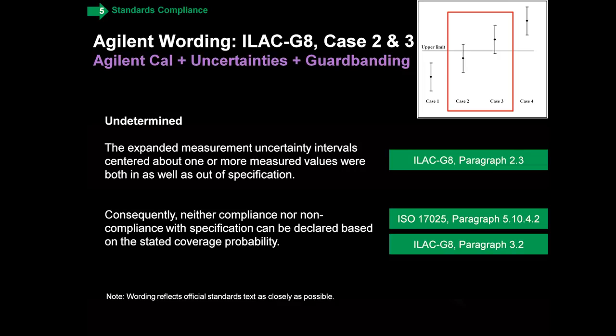There is also a service called 'Agilent Cal Plus Uncertainties Plus Guard Banding,' and this one gives pass or fail — or in the case of either case two or case three, where you measure just inside or just outside but the uncertainty crosses, the standard says you should really call that undetermined, so you can't say whether it passed or failed. We do report the measurement result, so any customer wanting to know 'was I in or was I out?' will be able to see that on our measurement report, but in terms of the designation the standard says to report undetermined, so we do with this service.